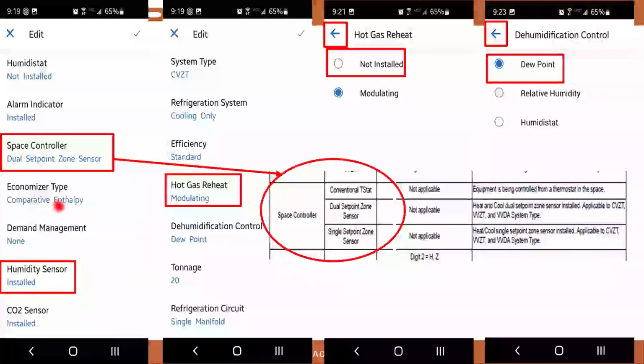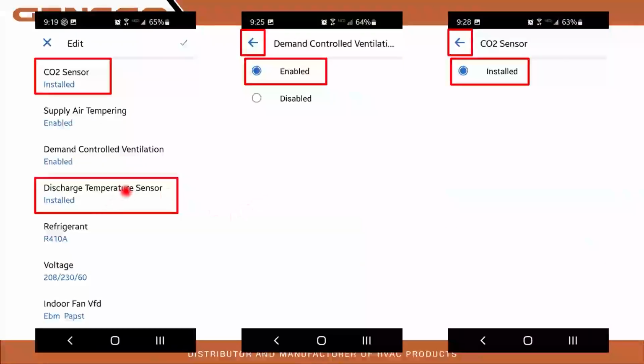Economizer type, comparative enthalpy. If you have this set up as comparative instead of dry bulb economizer, we're just using the temperature of the supply air through that discharge air temperature tube, and I'll show you that. Enthalpy, we're using multiple sensors inside the return air cabinet. We're checking humidity and return air temp too. So then it's going to be looking for all those sensors. And if you don't have all those sensors, it prompts the alert. Discharge air temperature sensor, you're just going to go in. Setup is pretty smooth. Once you play with it a few times, you start to understand its navigation.